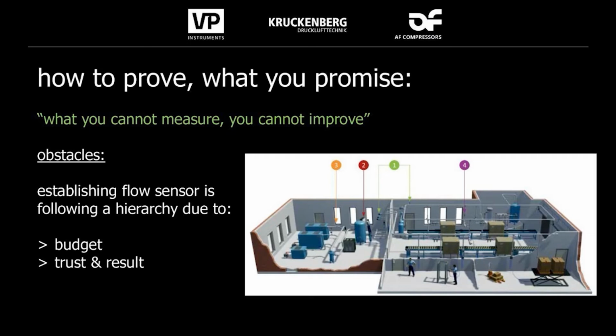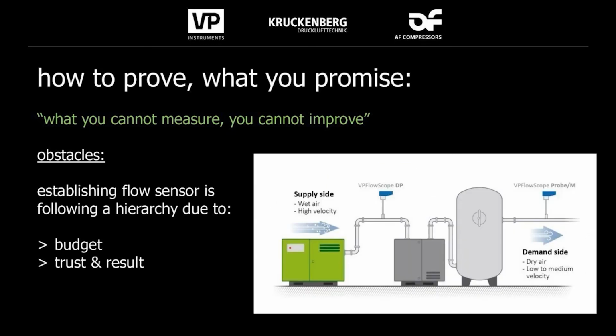Of course, the pipelines were not created to consider flow measurements. They were created 10, 15 or 20 years before. Nobody thought about measurements, and the lengths are not making it possible to establish a flow measurement, or you will have pipelines not monitored. So we started here with individual production lines and production rooms, and single compressors. So we were using wet air flow measurements, where you cannot use thermal mass measurements because they would be destroyed or maybe damaged.